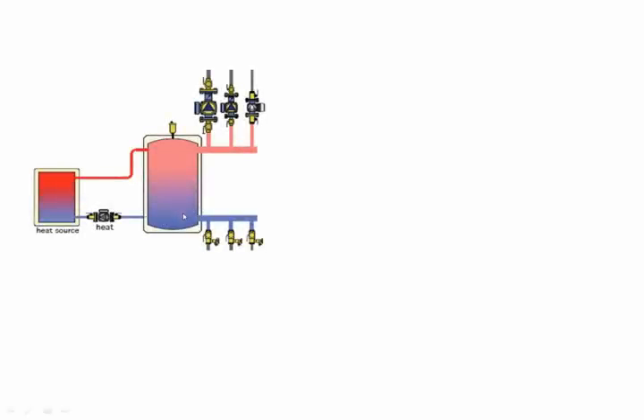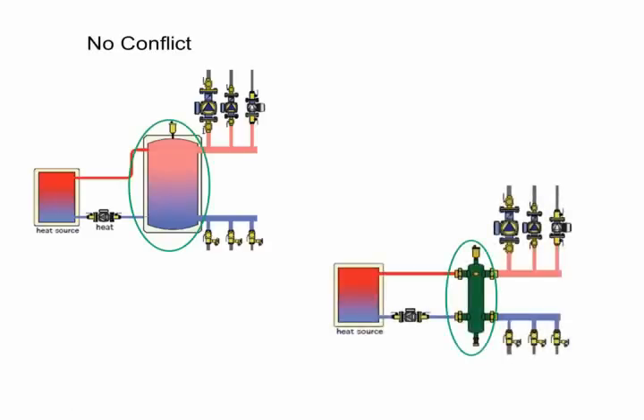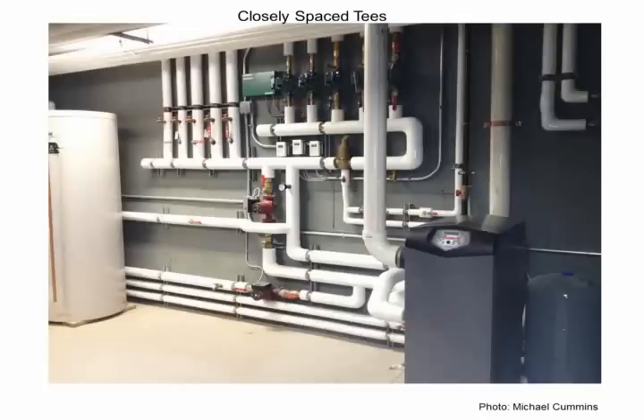Alternatively, instead of closely spaced tees, we could have taken a buffer tank. Like a pair of closely spaced tees, we have 4 ports: out to the system, back in from the system, and then the primary side. We might use this if we need some type of buffering in our system, if our zones are highly zoned over here. Or we could use hydraulic separators such as this. Now, hydraulic separators have a couple other features that closely spaced tees don't have, and that's air elimination and dirt elimination. Now, let's take a look at hydraulic separation here. But first, closely spaced tees.